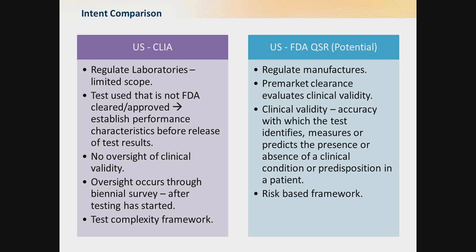There is a very different framework, particularly when it comes to test complexity versus risk. Test complexity is used as the means for CLIA regulation, whereas the FDA quality system requirements will implement a risk-based framework. In many ways these can overlap — for example, if a clinical laboratory is using proprietary algorithms, these will be both complex as well as bring new measures for risk management.